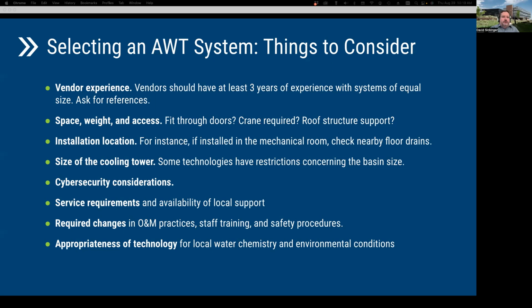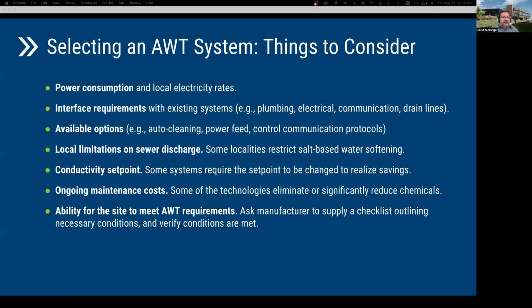Continuing on into the next slide, again, things to consider is whether or not the AWT system requires power, taking into account electricity rates and accessible feeds in the location where you're going to install this, such as a 120, 240, or 480 volt power feed. Piping to and from the cooling tower system can impact or be an expense, so location and proximity to the cooling tower system is key. Ask about available options. Some of these systems have an auto cleaning mode that could potentially save significantly on O&M cost.